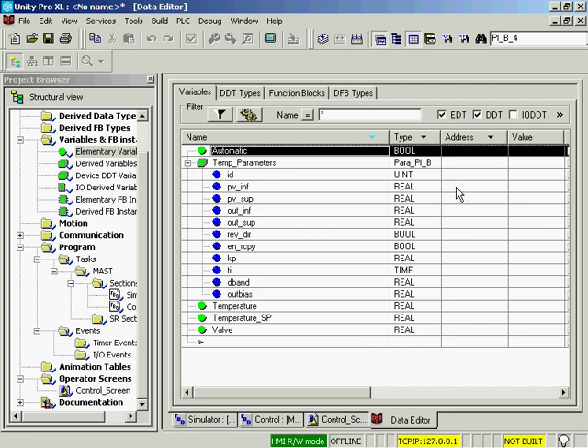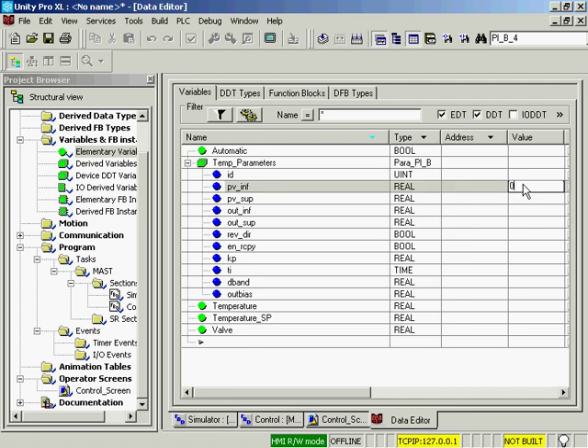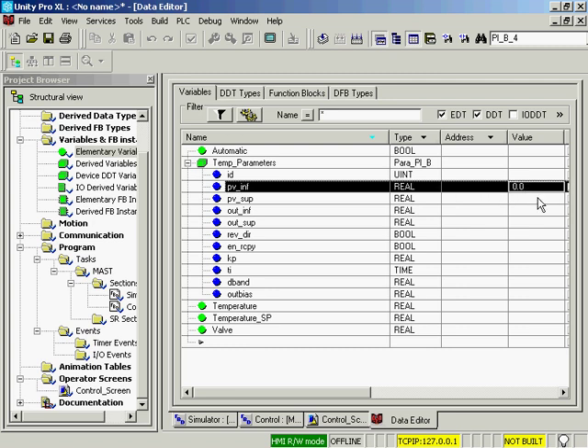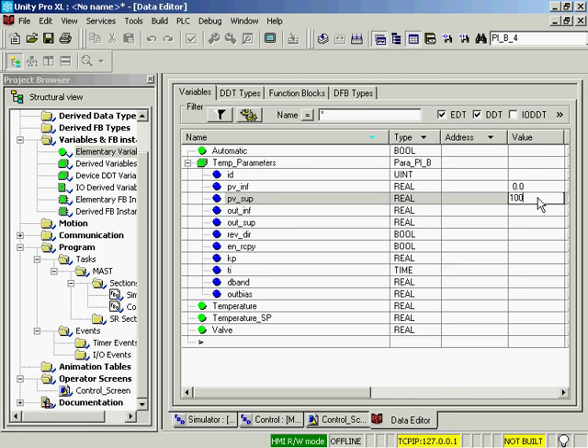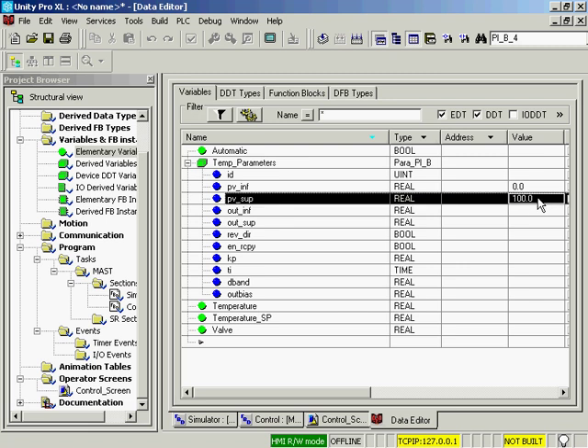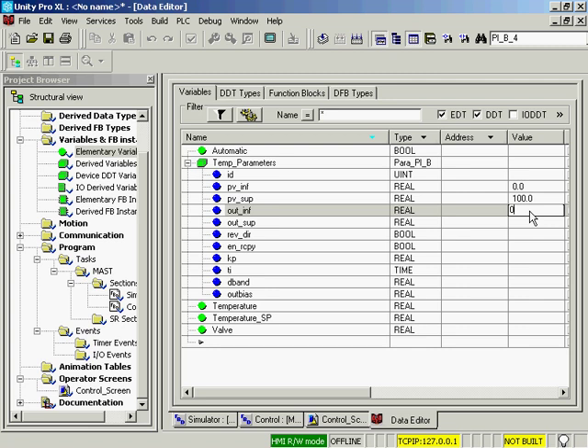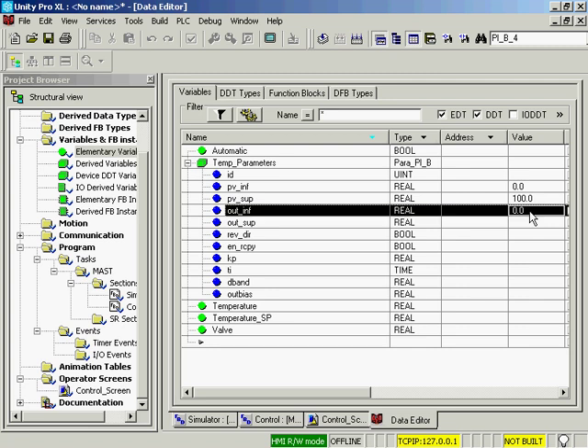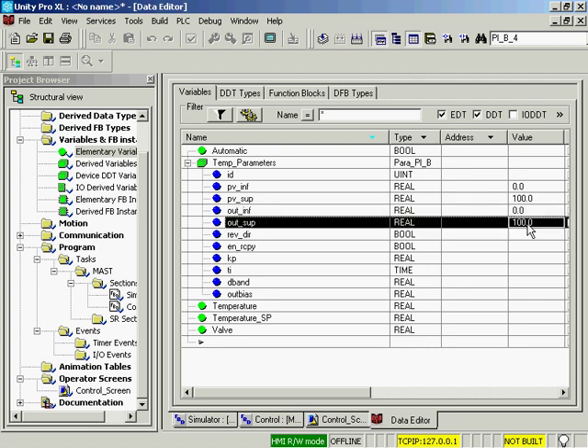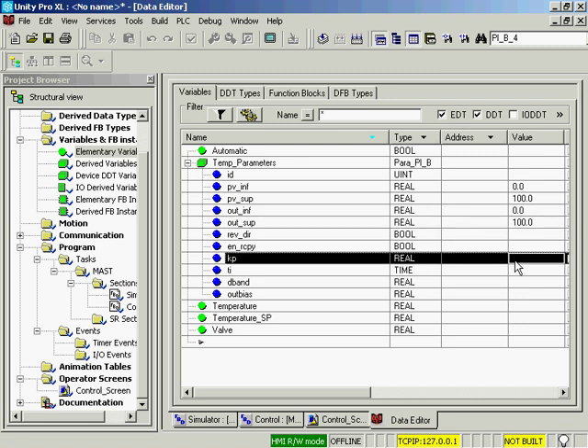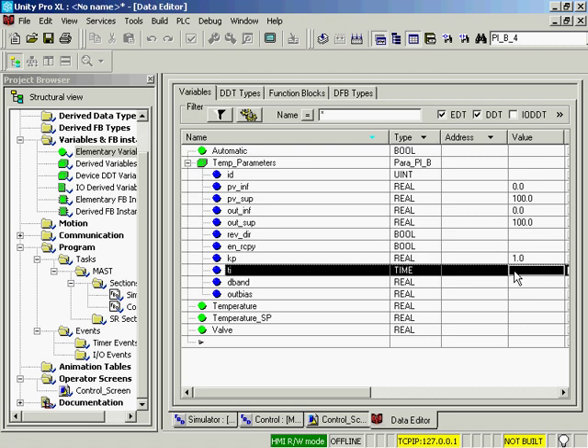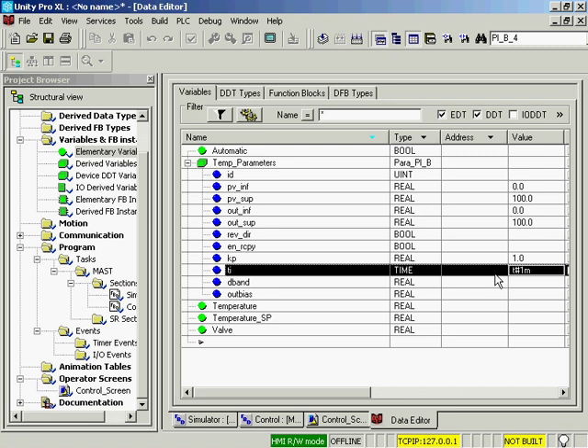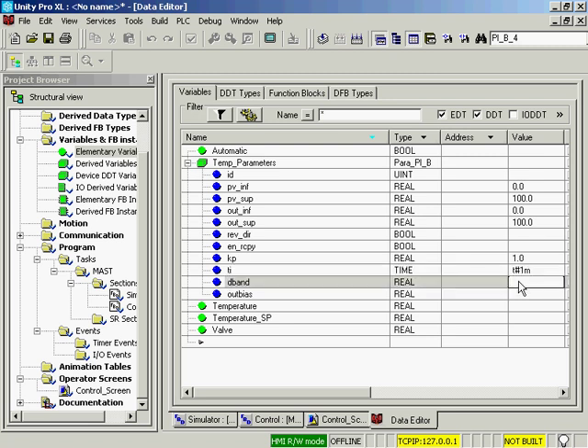In our variables, we'll set some of the temp parameters. Our process variable low value is going to be 0. We'll scale it to 100 just to make life easy. Our output, the valve, will be from 0 to 100 as well. We'll set our proportional gain up to 1. And we'll set our integral time to be 1 minute. That is a 1m for minute. And I'll go ahead and set a little bit of a dead band of 0.25 degrees.